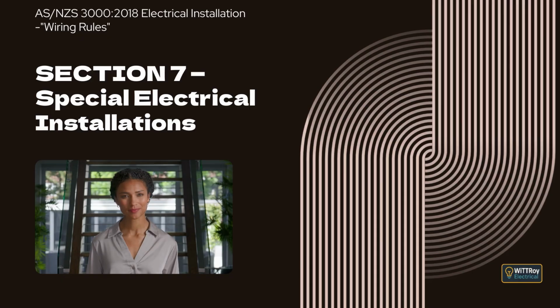Clause 7.2.3.4 Arrangement. This clause explains that where a supply isolating device is installed, it must be capable of breaking load, such as a load break switch or circuit breaker. It also explains that discrimination must be achieved between protective devices if a circuit breaker is used. The clause notes that additional requirements may apply, including the ability to lock the device on and labeling to restrict operation to authorized personnel only.